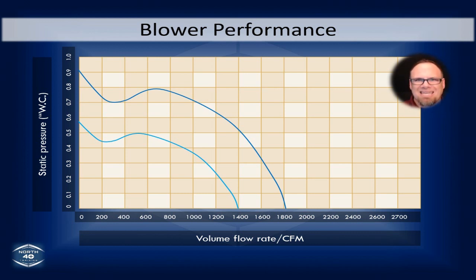These systems get their maximum efficiency by allowing the most amount of airflow to go through there, so they move the most amount of air while having it at the right temperature when they're doing it. That helps dehumidify and cool in the summer and heat in the winter time, but it also, on a larger scope, over the long haul of this system's life, it will preserve that life. It won't be working as hard. It won't sweat in places it's not supposed to sweat. It won't have problems that go unseen for years and years that eventually lead to large, expensive problems. So blower performance is a huge, huge factor in everything that we do.